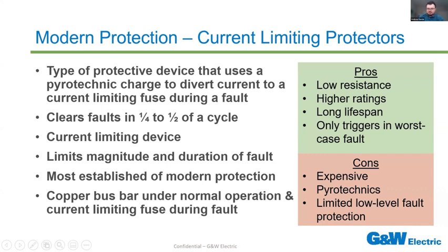It's important to note that this is just a copper bus bar under normal operation, meaning that the losses are very low, and it only becomes a current limiting fuse if a fault is detected. So once again, pros: it's a copper bus bar under normal operation, so it's low resistance. It can go up to much higher ratings than alternatives, an order of magnitude higher continuous current rating relative to a current limiting fuse. It goes up to 4,000 or 5,000 amps, depending on the voltage rating. It has a long lifespan, 20 years and additional years beyond that if you follow a maintenance program from the manufacturer.